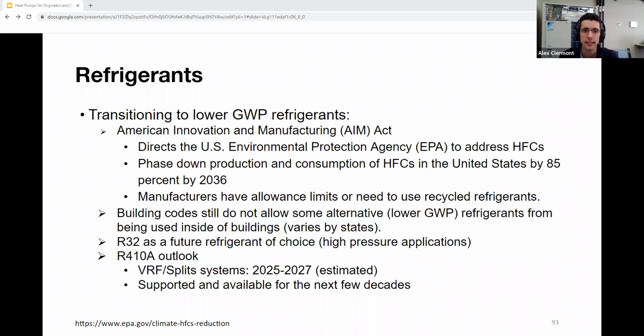Now, when you're looking to do heating, this is where you need those high pressure refrigerants. But currently, again, you cannot have R32 through occupied space. It's going to be a few years before that's allowed at the federal level, and then a year or two to get it adopted by states. It's estimated that we're probably still 5 or 6 years away from seeing R32 in VRF and large air source heat pump systems. R32 has already started in small one-to-one split systems, mostly for residential applications, in some states that allow it.